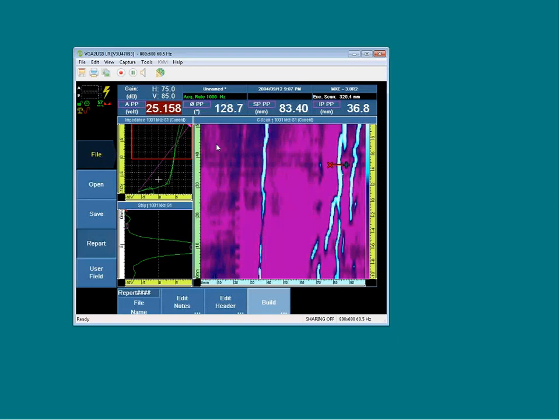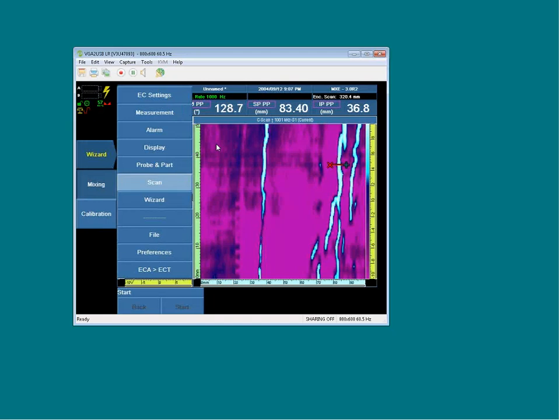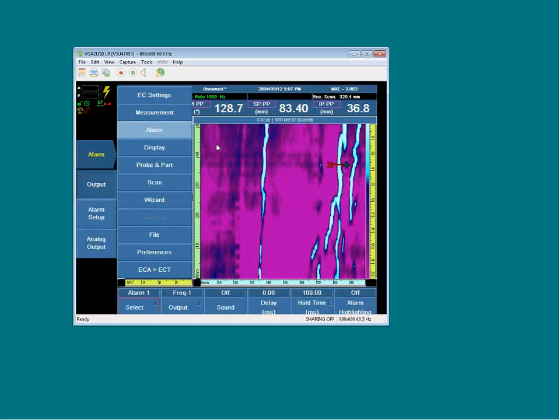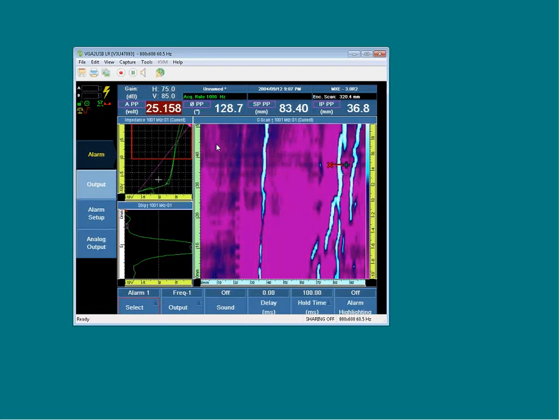There's a last feature that I like showing with that application is called the Alarm C-Scan. It's basically the ability to display the signals as a sharp, clear go-no-go, gray or red signals based on the alarm box that is found in the impedance plane. So that's a more advanced eddy-current representation or eddy-current way of doing the test. If we look at those signals on the impedance plane, you get to see a kind of a blob, a green signal going up on the impedance plane into the box. So whatever's outside that box would be accepted. Whatever's inside is deep enough, has enough amplitude to be rejected.